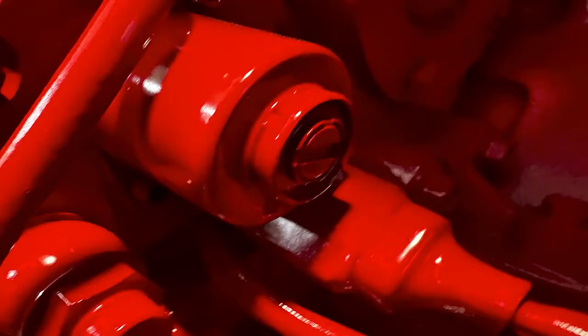So let's take a look. So here's that actuator as a close-up of it. On the bottom is the harness going to it, and that goes up into the side of that solenoid. That's what looks like a screwdriver slot on the back, is just the end of the shaft in the solenoid. It's not a screw. There's no adjustment there. Do not try to turn that. If you turn it, you have damaged your actuator.